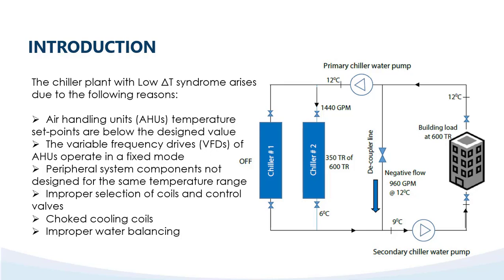This kind of low delta T syndrome arises when components are mismatched. Point number 5: improper selection of coil and control valves for the supply and return temperature. The supply is 6 degrees and return is 12 degrees Celsius. For this temperature range, the coil is supposed to have 4 row coils. If it is 3 row or 2 row, this will lead to low delta T syndrome. Choked cooling coils as well as improper water balancing also lead to this kind of situation.